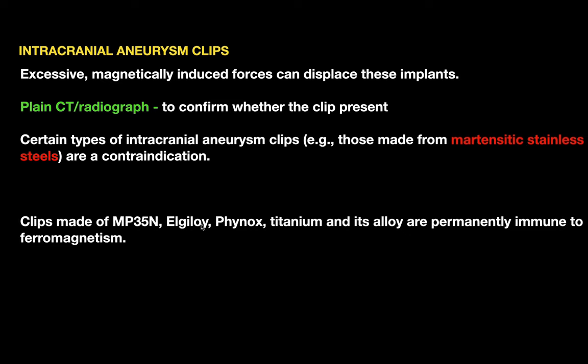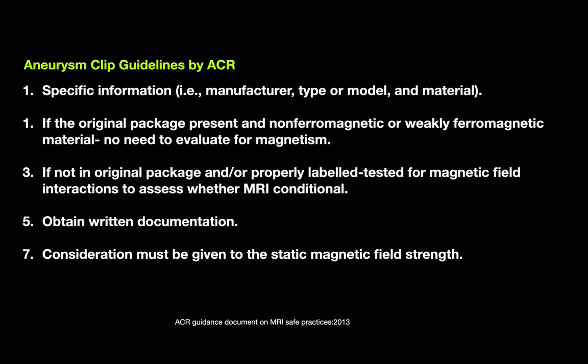ACR aneurysmal clip guidelines: specific information on manufacturer type, model, and material should be obtained. If the original package is present and material is non-ferromagnetic or weakly ferromagnetic, no evaluation for magnetism is needed. If not in the original package and properly labeled, testing for magnetic field interactions should assess whether MRI is conditional or not. Written documentation should be obtained when scanning such patients, with consideration given to the static magnetic field strength.